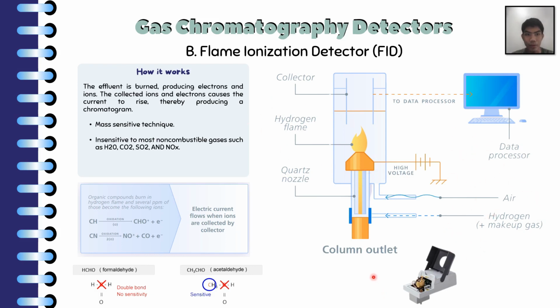The carbon in a sample carried into the detector on a carrier gas is oxidized by this hydrogen flame, which causes an ionization reaction. The ions formed are attracted by a collector above the flame in an electrostatic field, wherein the components are detected. Additionally, the number of ions produced is proportional to the number of reduced carbon atoms in the flame. Hence, this technique is a mass-sensitive destructive technique.